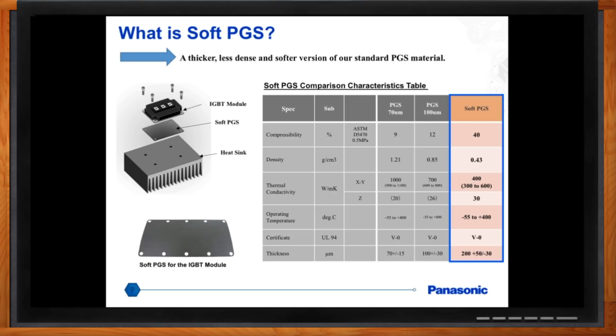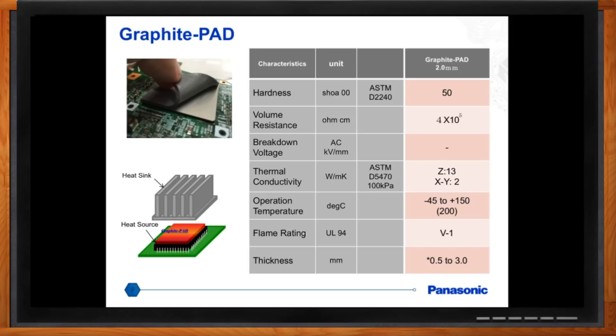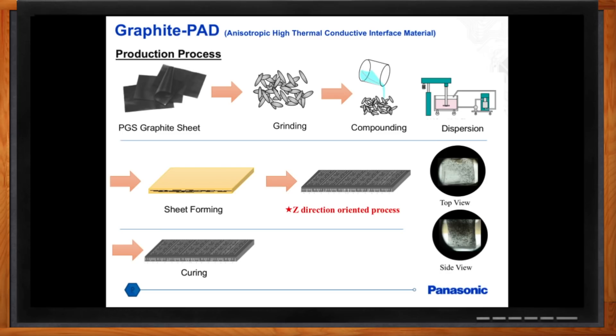Another product is the Graphite Pad, which has a very strong Z-direction conductivity capability. Gap pads typically range from 1 to 5 watts per meter Kelvin, whereas this material has a thermal conductivity of 13 watts per meter Kelvin. It also has high compressibility up to 60%, and thickness offerings from 0.5 to 3 millimeters. As for how it's made: the PGS graphite sheet is ground into little flakes, mixed with a silicone resin, formed into a sheet, with every flake oriented in the Z-direction — which is what delivers the high through-plane conductivity.